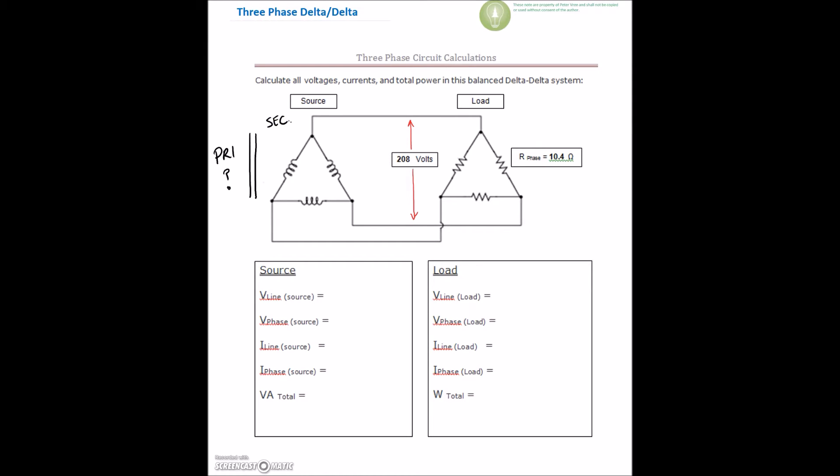And we can see here with the values that are given that the voltage right here is 208 volts. So I have a delta secondary feeding a delta resistive load. They're balanced in that each of these guys is 10.4 ohms.